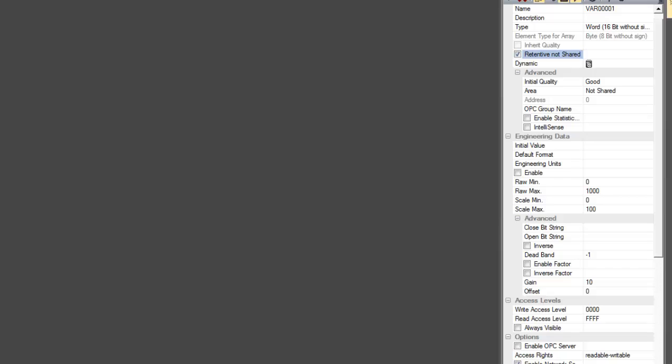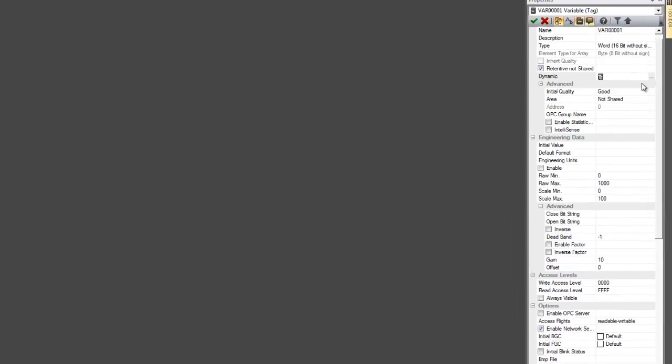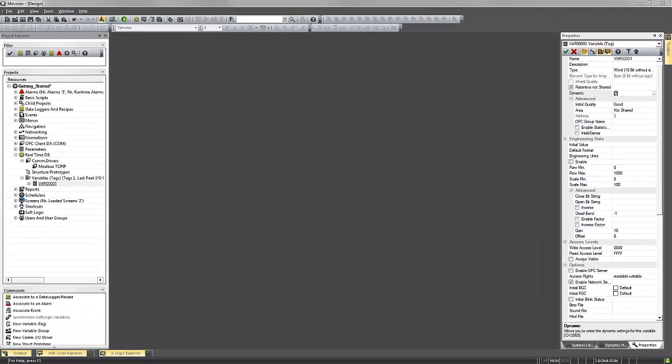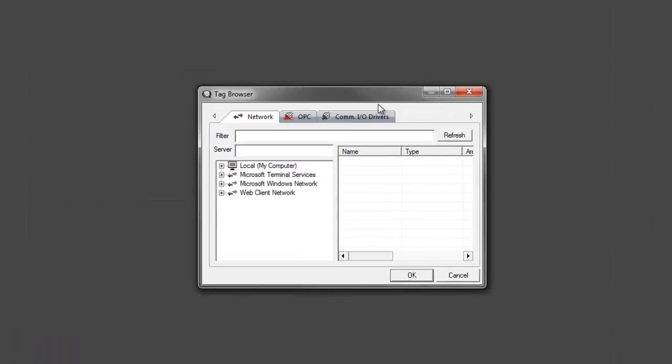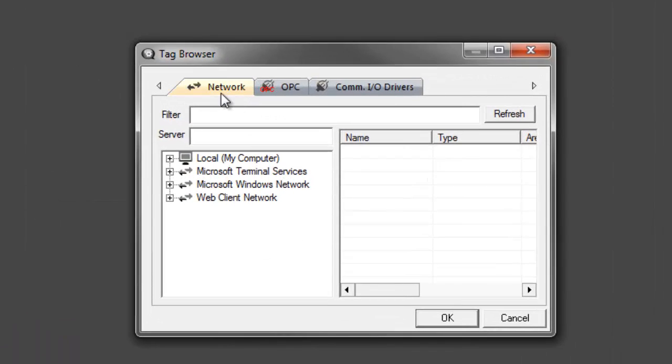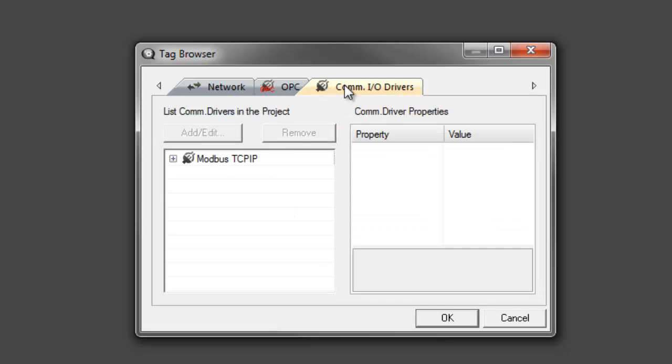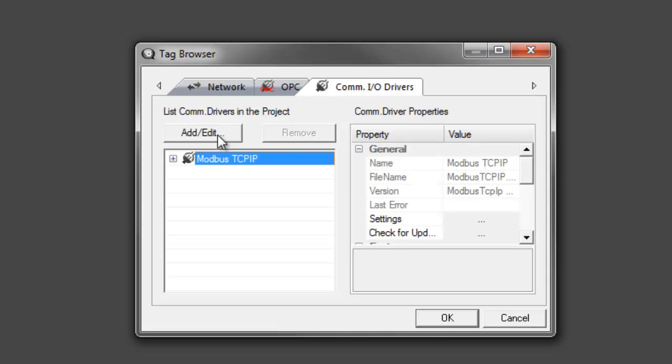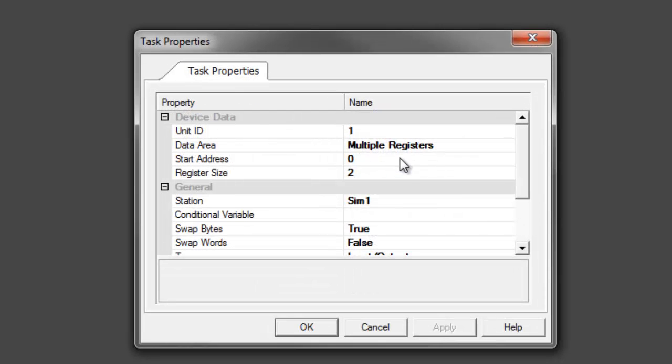To connect this variable to your driver or to a PLC address, we look for the property called Dynamic and open up the Dynamic Connection Manager. Here you can see we've got some tabs to connect to different items through a network, OPC, or your comm driver. We're going to select Modbus TCP IP, unit ID of one, multiple registers, and a start address.